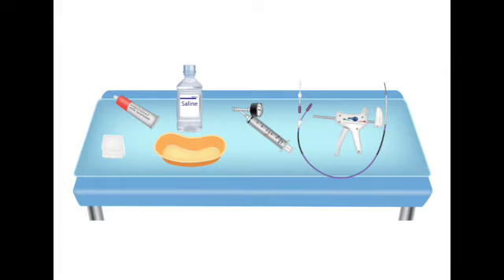Any air trapped in that system compromises the accuracy of your pressure reading, and worse, it introduces the risk of an air embolism, which is incredibly dangerous. So we have to perform two distinct, absolutely non-negotiable air expulsion steps. Let's walk through the first one, clearing the air from the syringe reservoir itself.